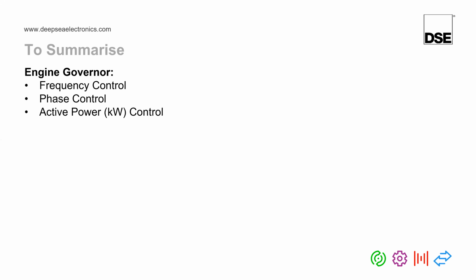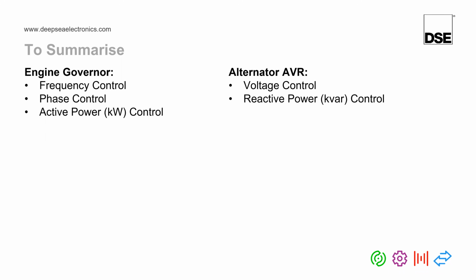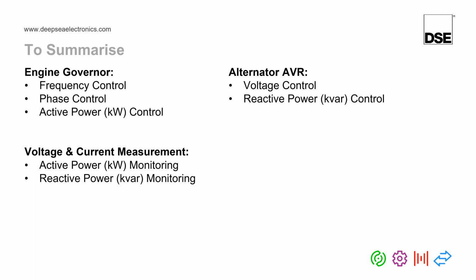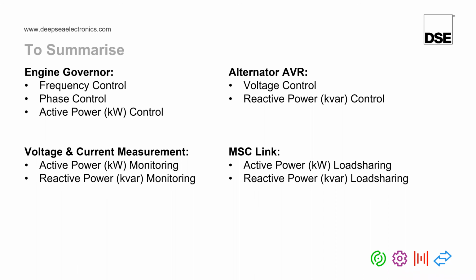So just to summarize what we've gone through so far, the engine governor is used by the DeepSea module to control frequency and phase while synchronizing, but it's also used to control kilowatts whilst in parallel with another generator. We use the alternator's AVR for voltage control while synchronizing, but we also use it for reactive power control whilst in parallel with another electrical source. We use the voltage and current measurement of the DeepSea module to measure how much active power, kilowatts, and reactive power, kVAR, the generator is producing. And we also use the MSC link to instruct each generator how much power to produce in terms of kilowatts and kVARs. So you can see there, it's very important that the DeepSea module has good control over the governor and AVR, and it has very good measurement of voltage and current, and also has very good communication.